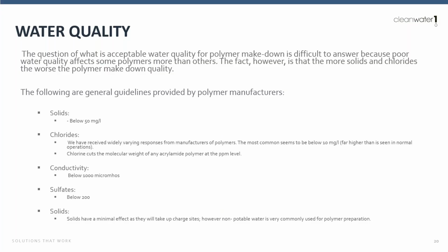We've had extensive discussions with different polymer manufacturers, and we've come up with some general guidelines. When we're talking about solids, we want to look below 50 milligrams per liter. Chlorides is a little bit of a tough one. We've received widely ranging responses from polymer manufacturers. Generally, the response is below 10 milligrams per liter.